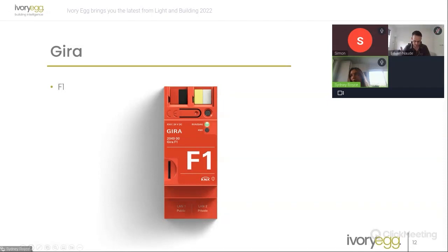So guys, these guys have been addressing an age-old problem. Everyone that's using KNX to do units, we've always got the problem of the multiple networks. We've got a building network or the owner's network or the backbone network, which runs the intercom, the metering and stuff like that. Then we've got each apartment, which has its own IP network. This device is the device that sits in between both.